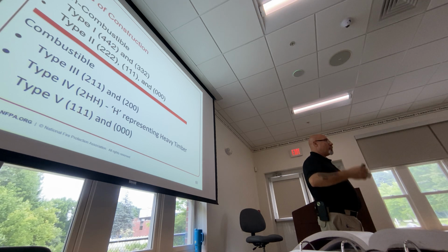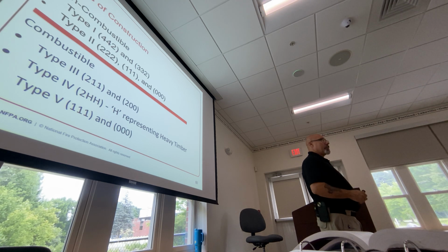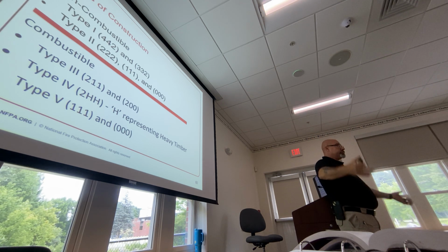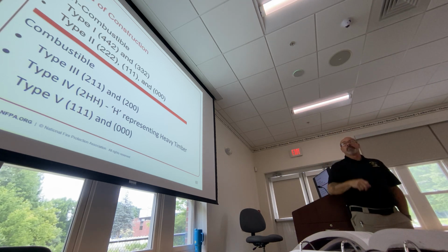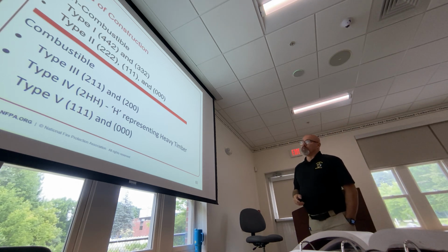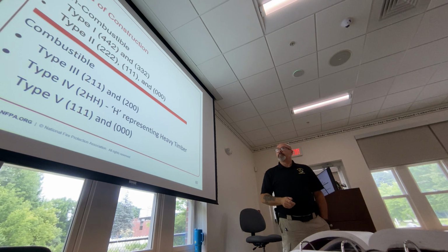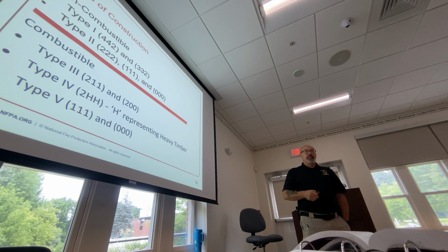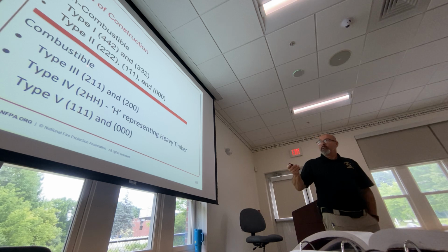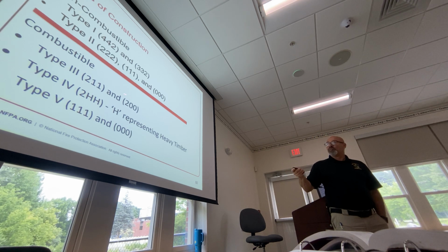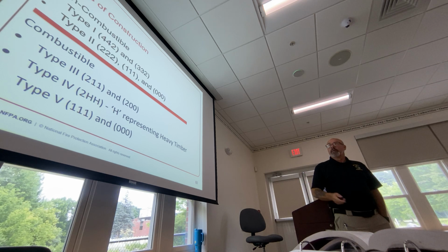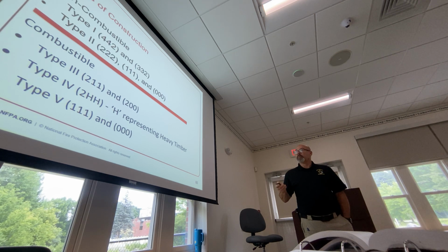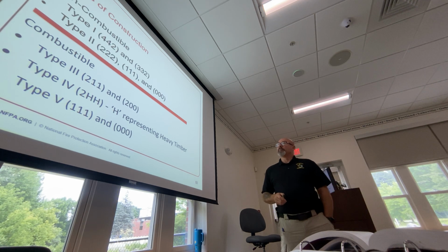They're constructed with masonry and wood. Okay, wood framing with brick on the outside of it. The floors and ceilings are all wood. That is an ordinary type 3 constructed building. They're brick on the outside, hence the 2 hour fire resistive rating on the outside. Everything else depends on how they've constructed it.